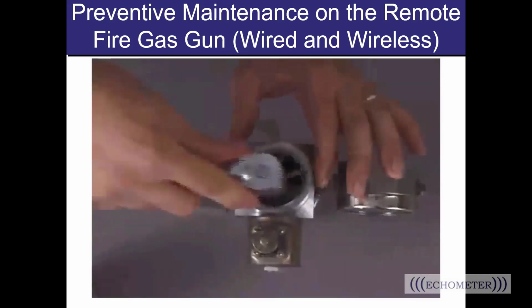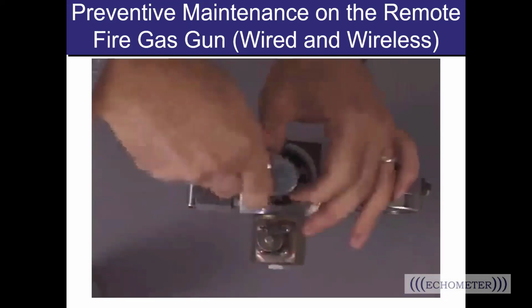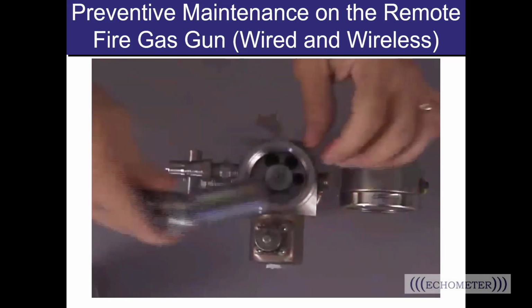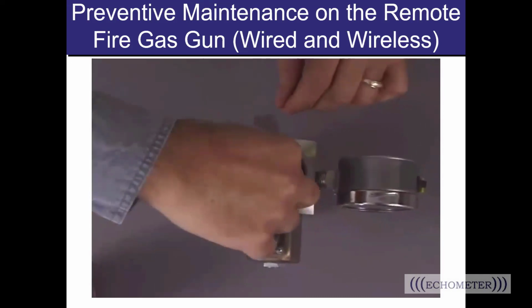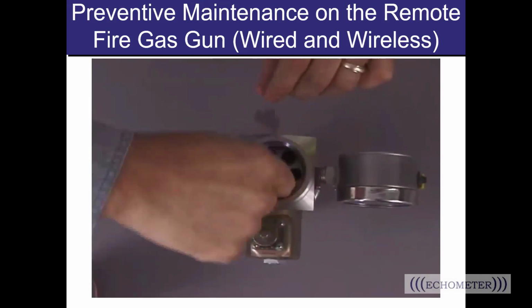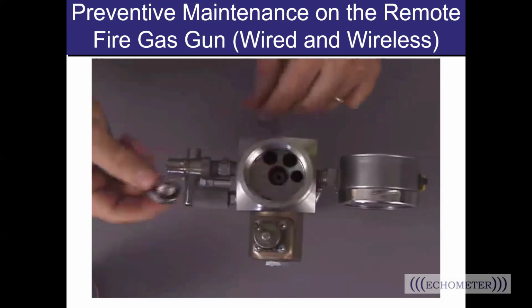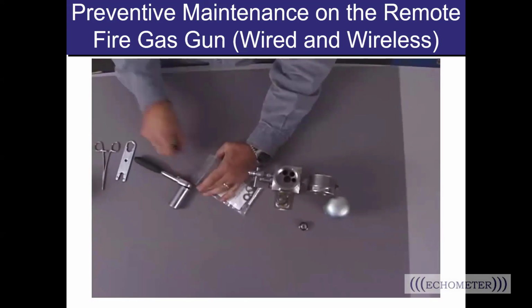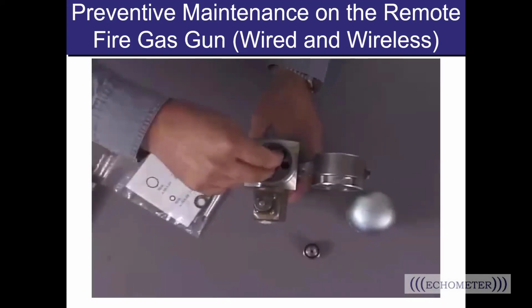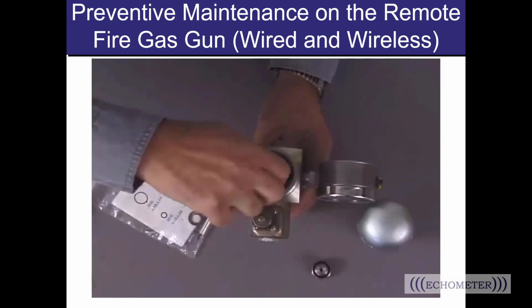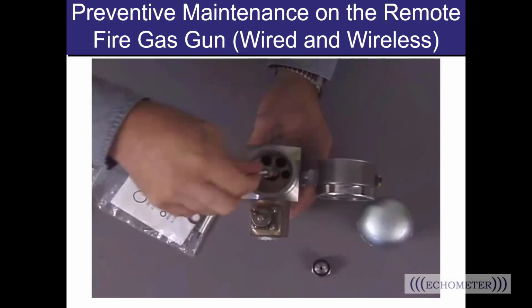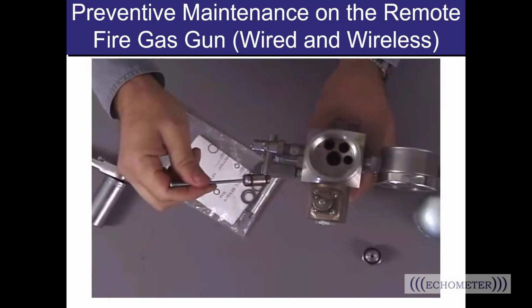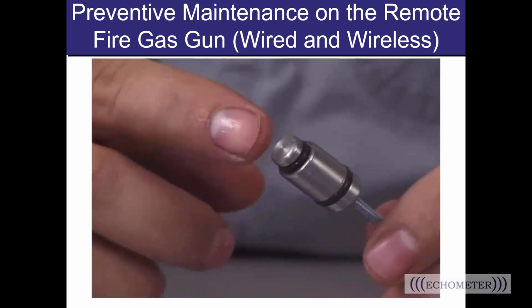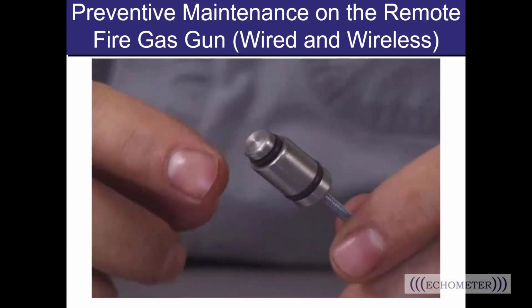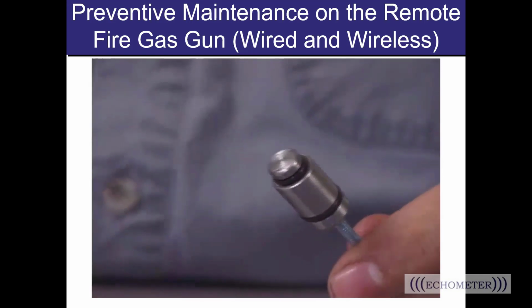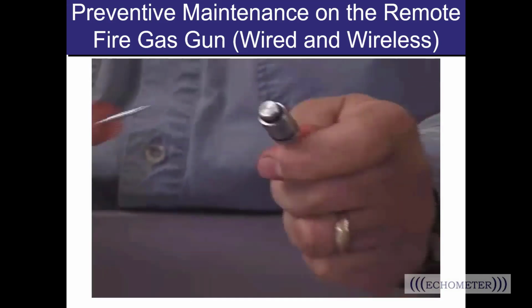Okay, so the orifice is where after that first little bit of gas pushes down the gas valve, the rest of it goes up through the orifice. So all of this, when you get into this complete assembly here, are things that you want to check and make sure that they're free of debris. You want to make sure that they're in good condition. And we have some great pictures to kind of show you a little bit further along here what some problems you can run into if you've got a clogged orifice, things like that.